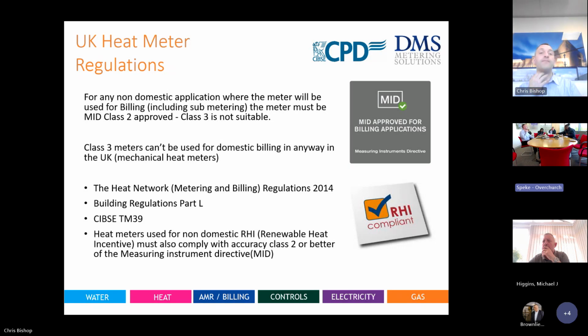in the UK market. Like I say, some of the regulations that you'll cover, and you've no doubt looked into, is the heat network regulation. So anything now that's a domestic apartment that's got a central plant room with more than 2 apartments is classed as a district heating network. Anything that's city-based, with regard to Sheffield, Newcastle, all the district heating networks that are happening around the UK, they have to have some form of metering either at building point or at entry level to the apartment, or a mix of everything. And that is a forced requirement now for anything that's new build. Anything that's retrofit old build, you have to do your feasibility studies.